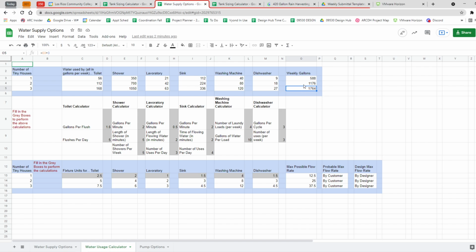That's your total water use per week. And you have to know that you can get that much water per week. Now, the next thing you have to know is, can you supply enough water if everybody wants it all at once? And so that's something called a fixture unit. How many GPM does one of these things use when you flush? Whoosh. Okay, and that's 1.6 gallons per flush, but they always list it at more fixture units.